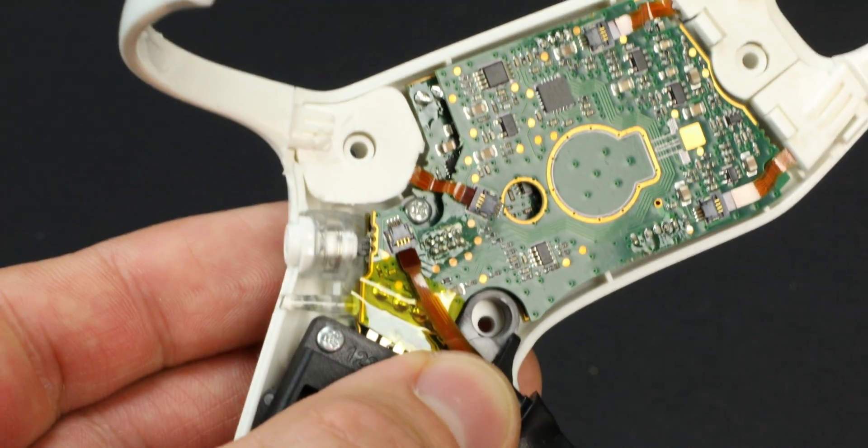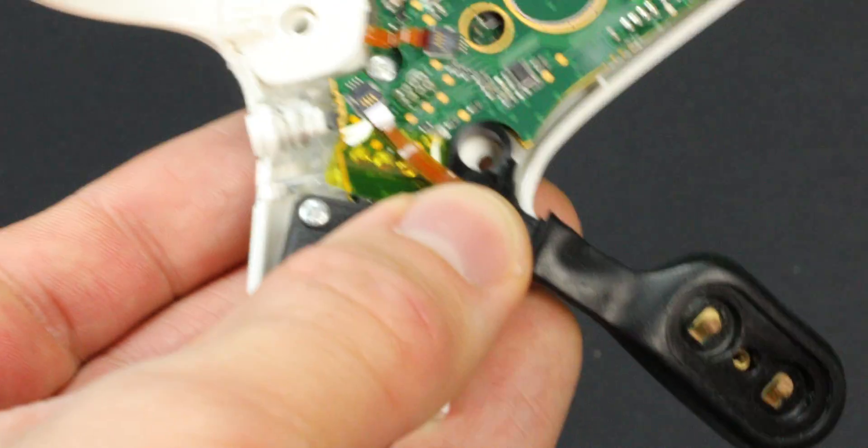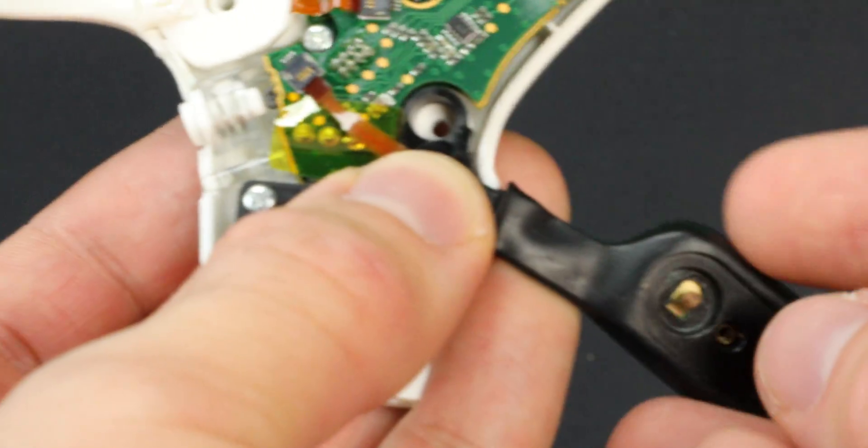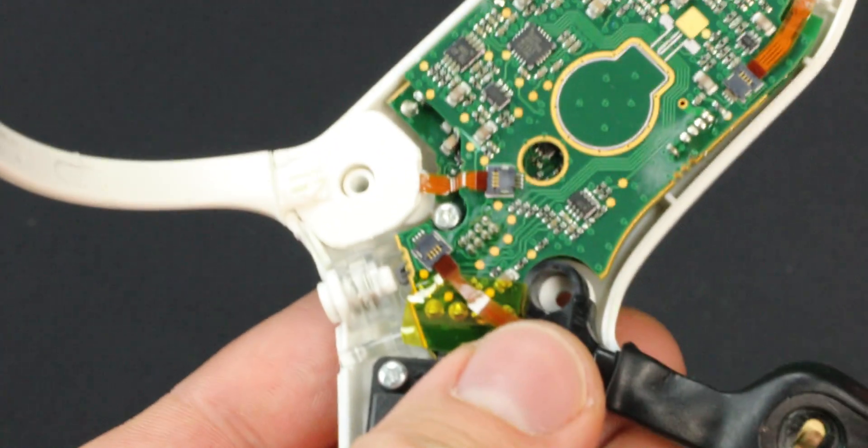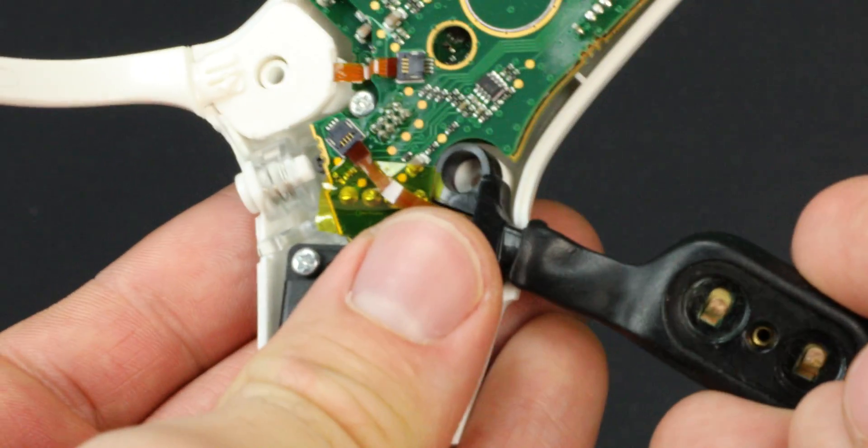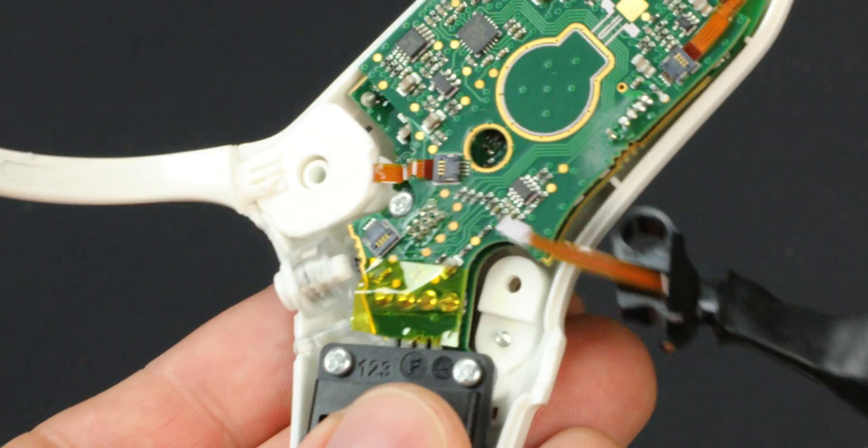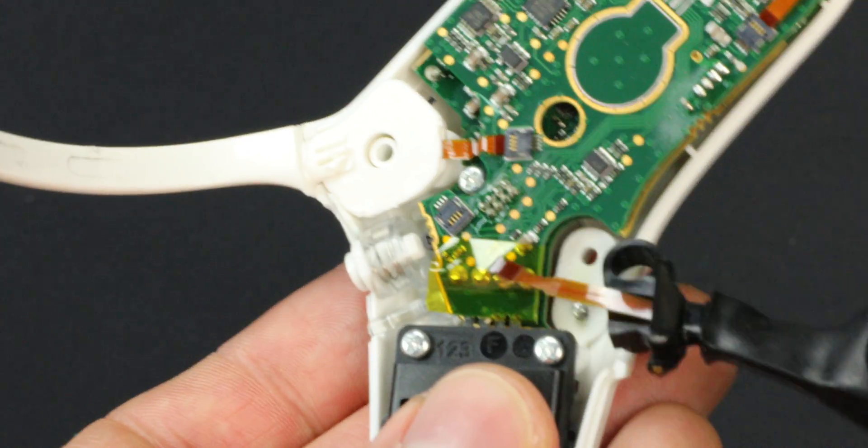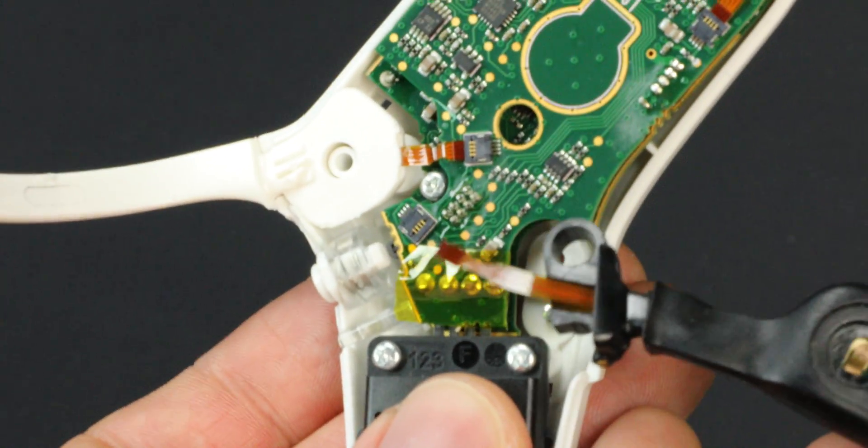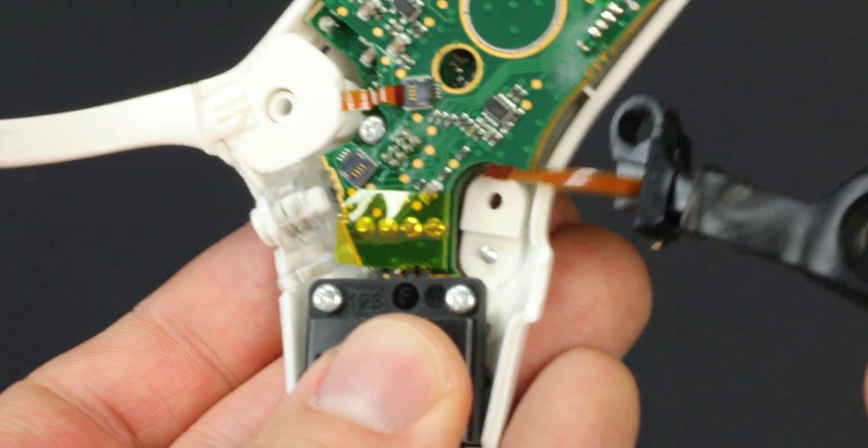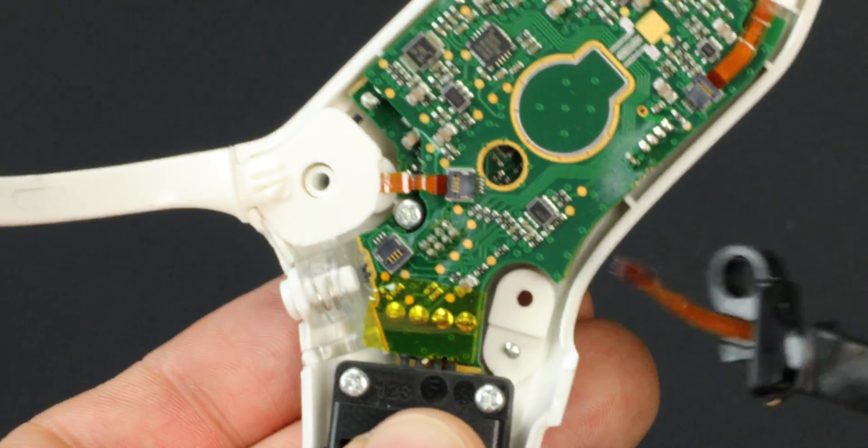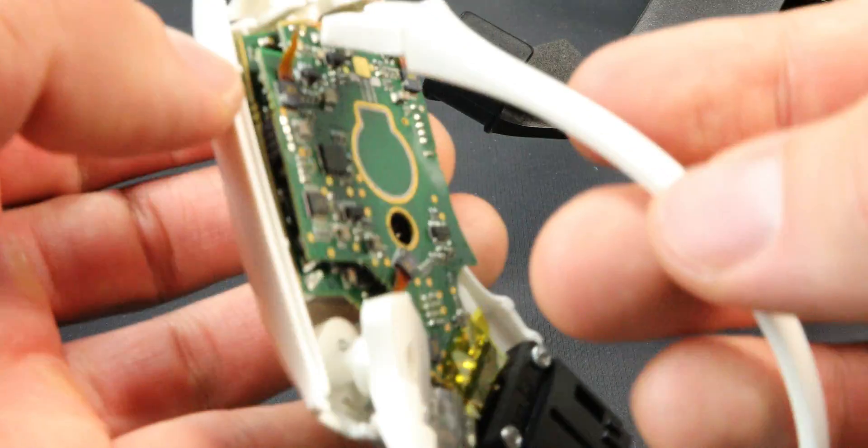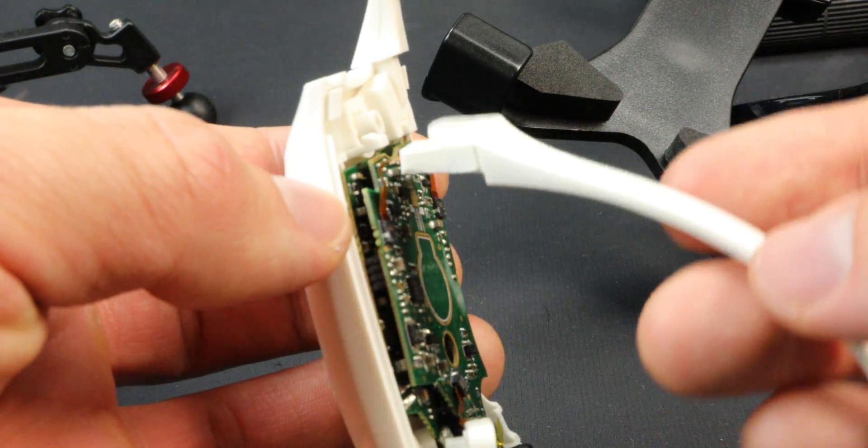All right, so one of the first things that I noticed is that the wiring from the reference electrodes that go behind your ear, when they were going into the circuit board, they actually came right out of the receiver as I was opening up the plastic covering. I'm not sure if that's what was causing the connectivity issues, but it could have been that the device wasn't properly grounded. When I tried to tug on the wiring of the other sensors, they were more securely attached to the receiver on the circuit board.